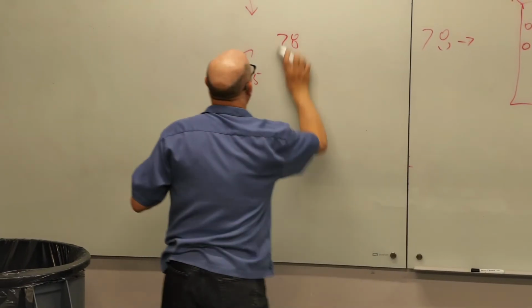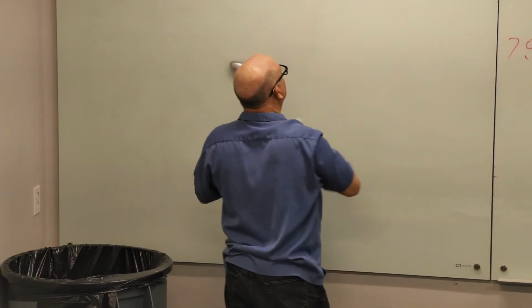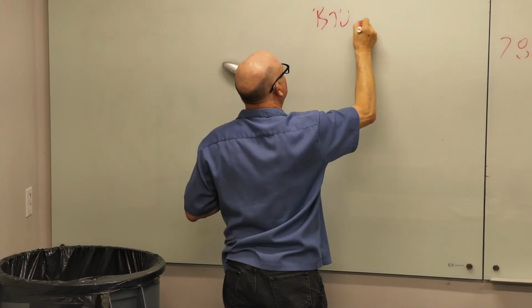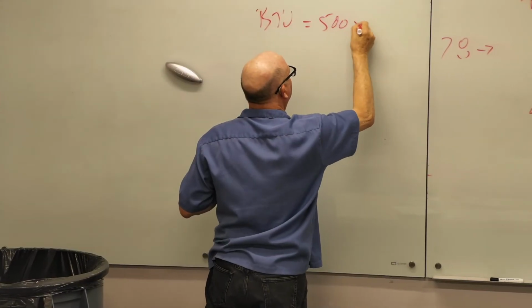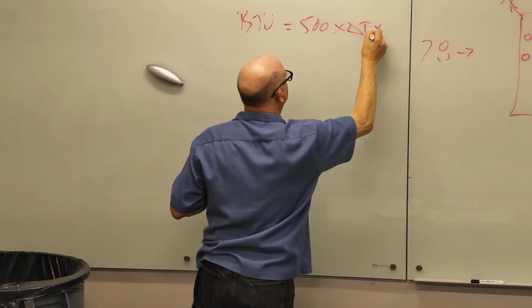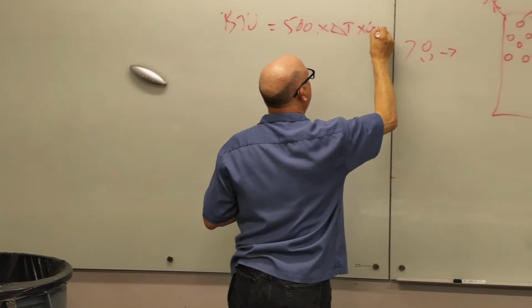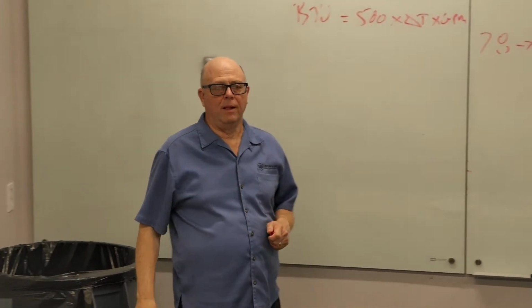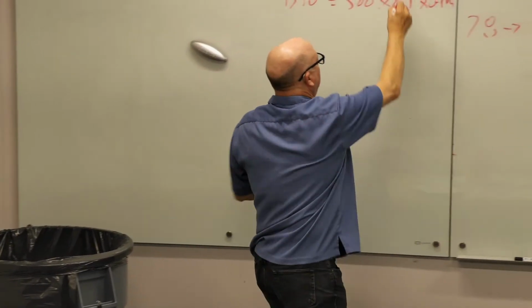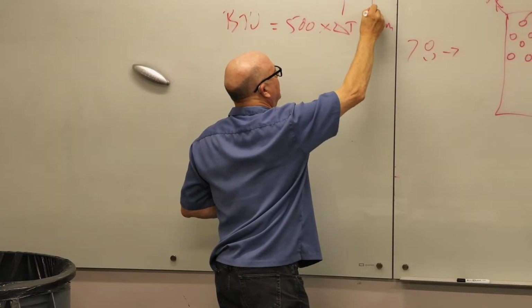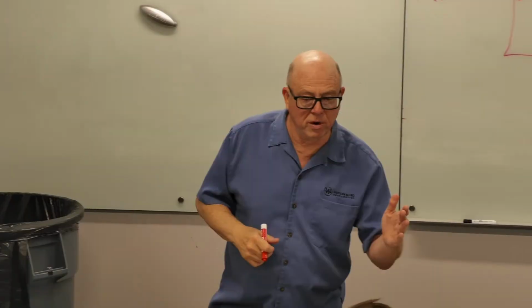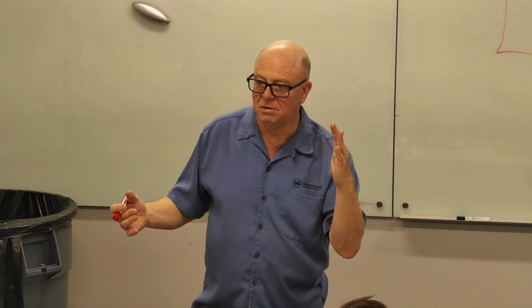So, the formula: BTUs equals 500 times delta T times GPM. If you want to take a really high rise, make this number big, that means you're making that number smaller, right? They're inversely proportional. If you took a 10-degree rise versus a 20, at a 10-degree rise, you'd need twice as much water flow. At a 20-degree rise, you'd need half as much water flow.